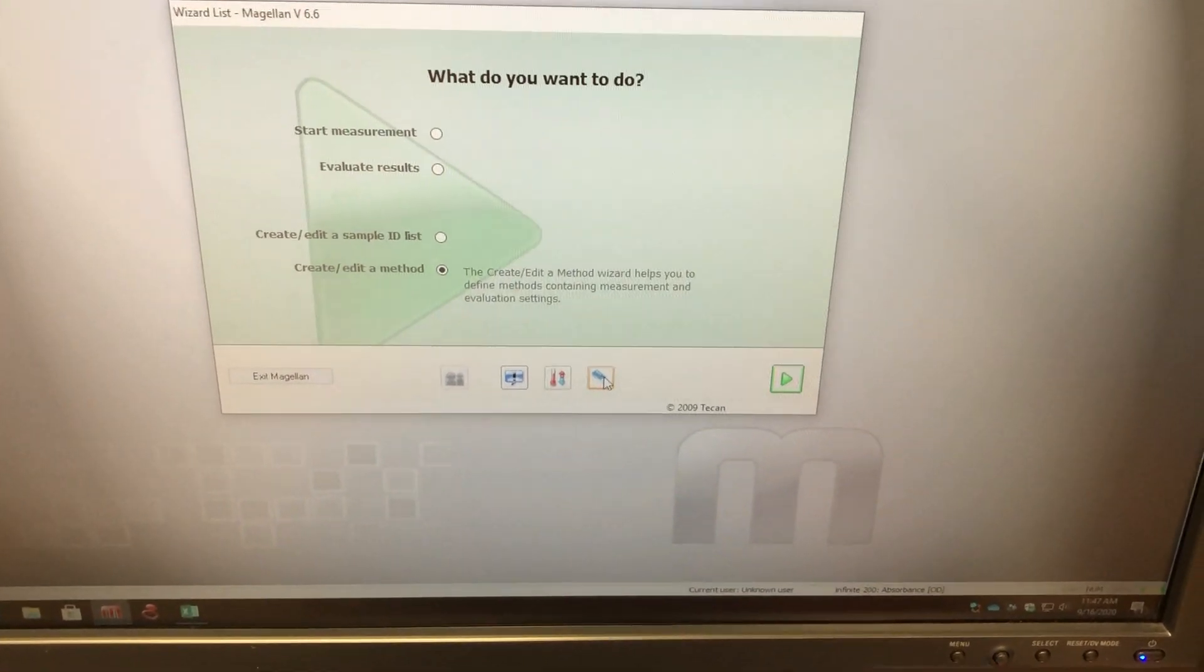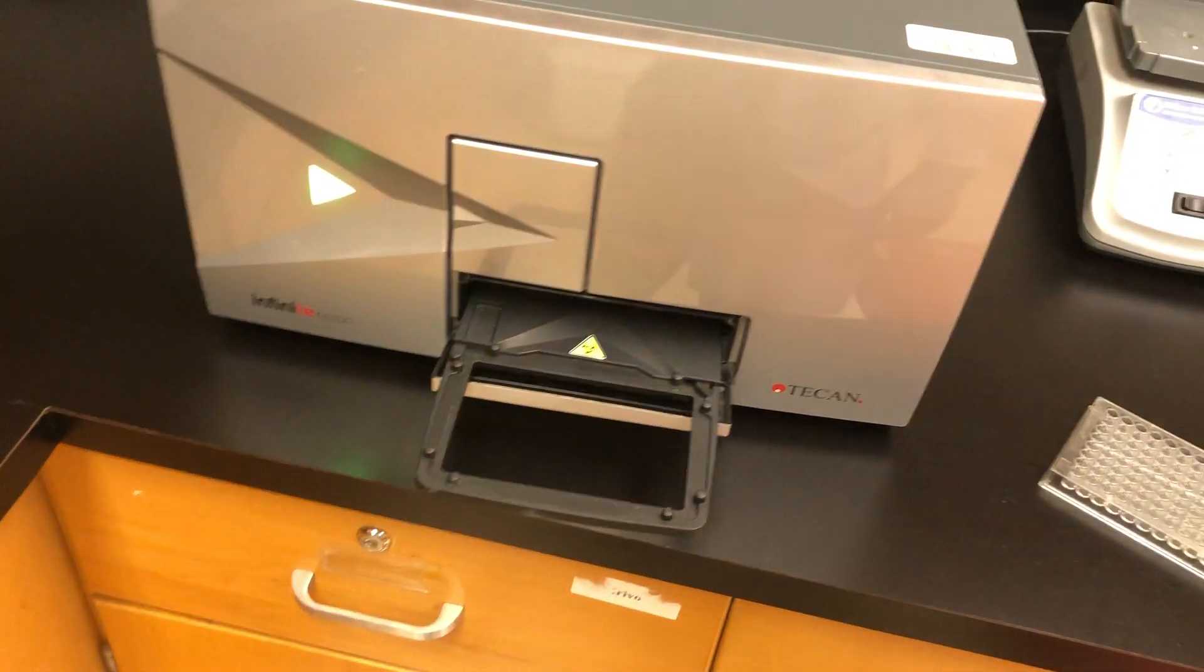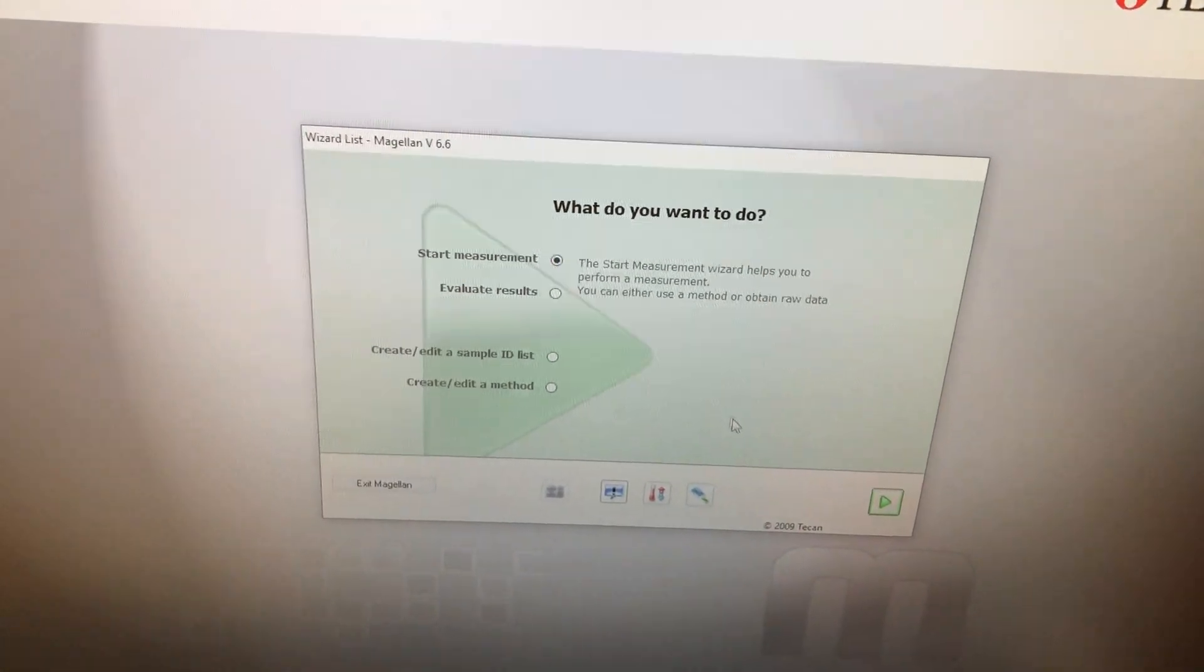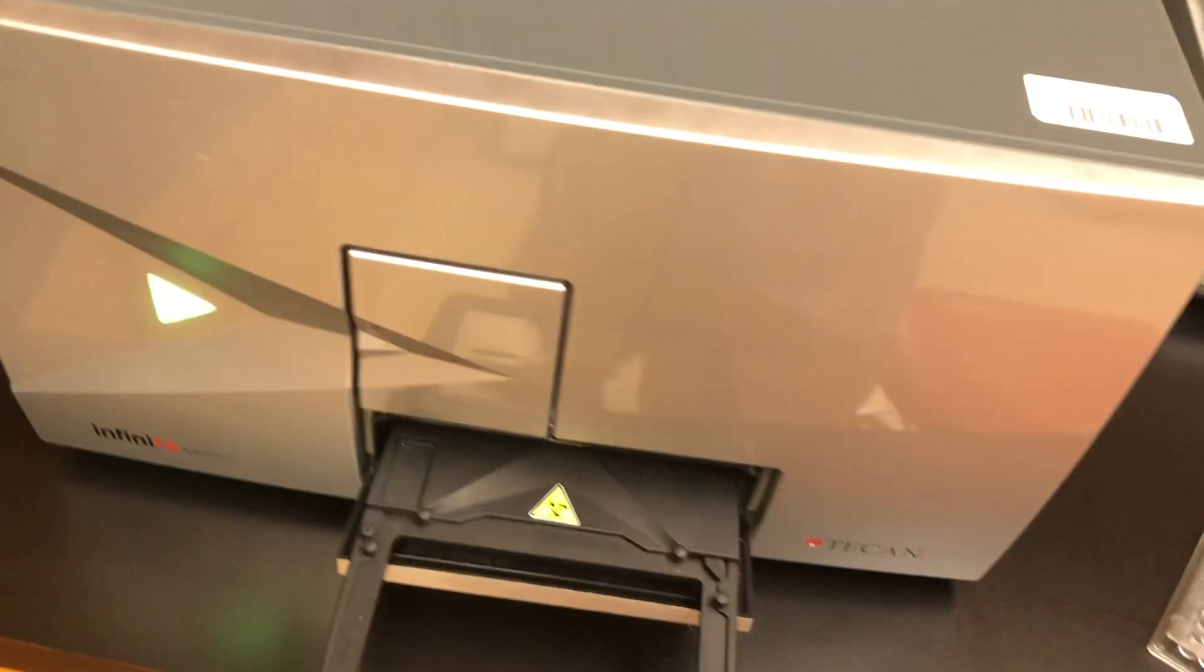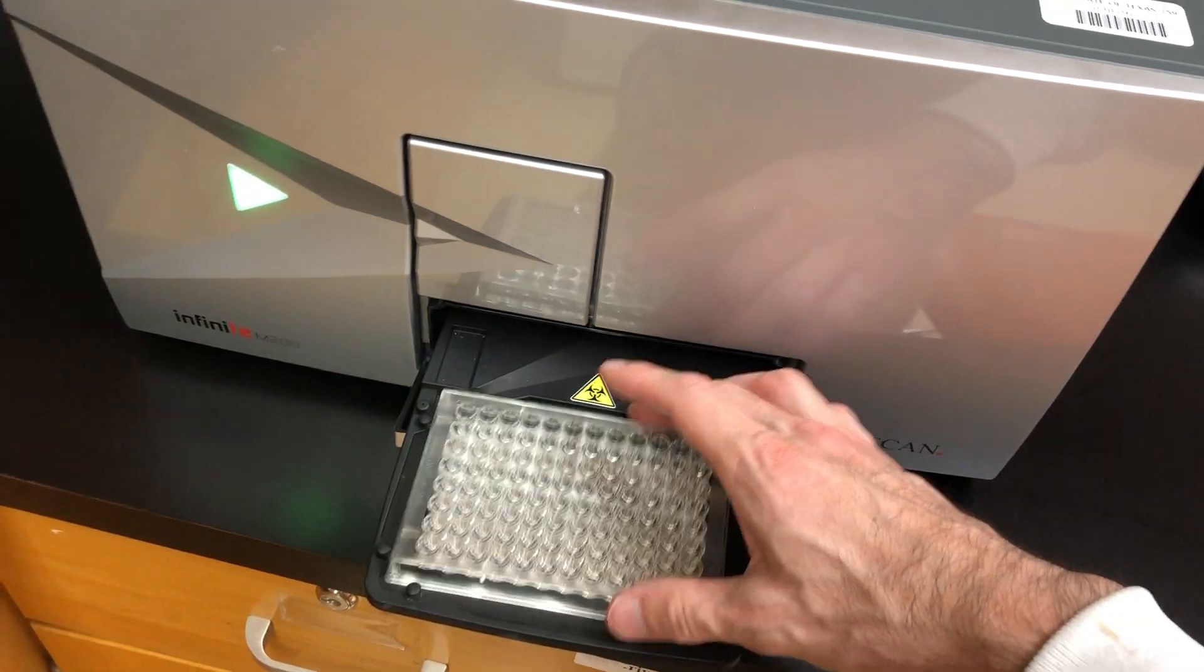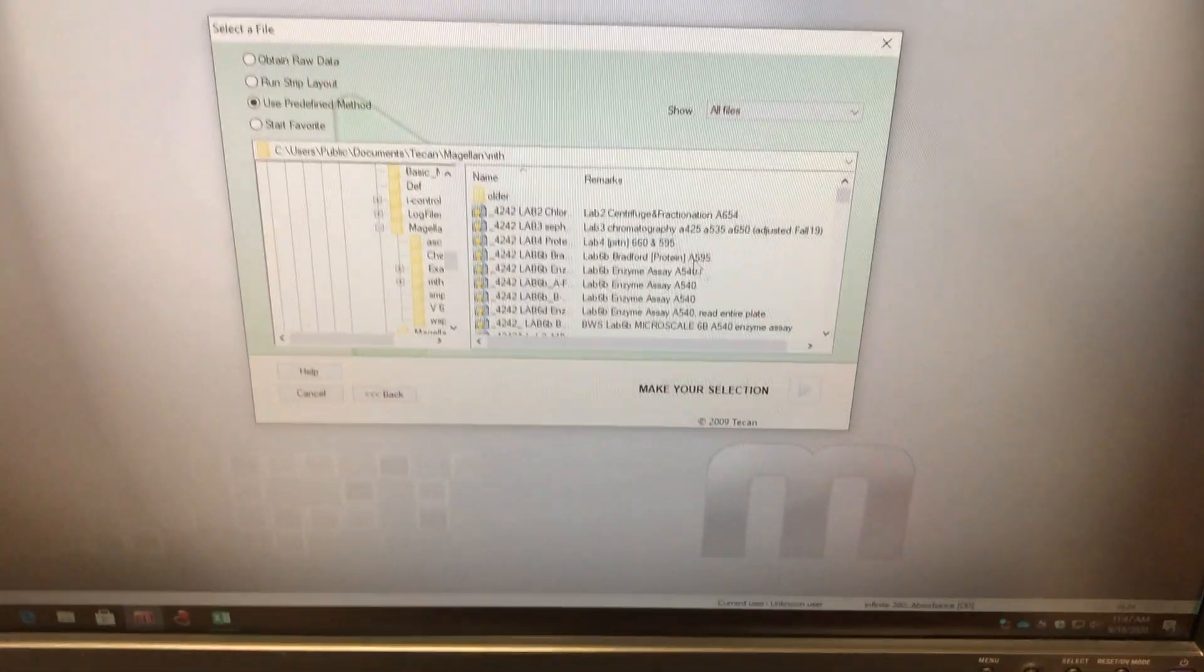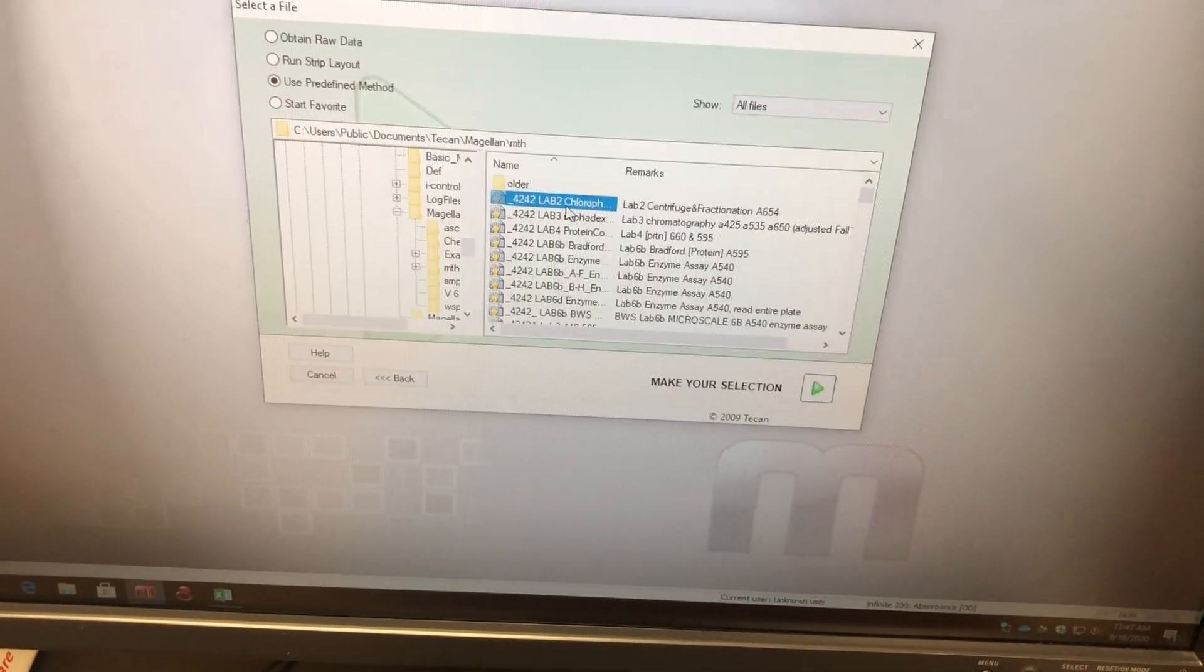And this is saving the internal file. Just go ahead and save it. And maybe now we're done or we're going to measure another plate. We can click this little open plate button. And once you've got a protocol set up to your liking, instead of going through that edit method, you could just click Start Measurement. Go forward. Put our plate in here. Start measurement. Now you just select it and you don't have to mess with any of those options. Now it's measuring based on the last options that we set.